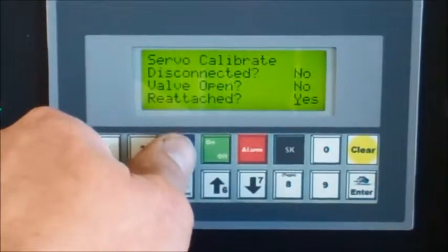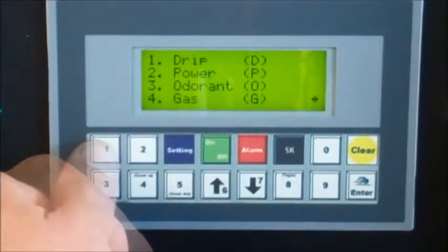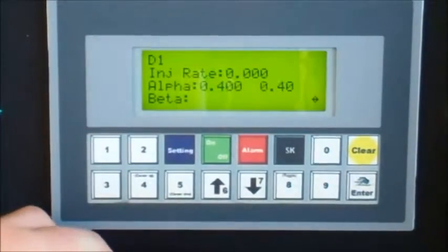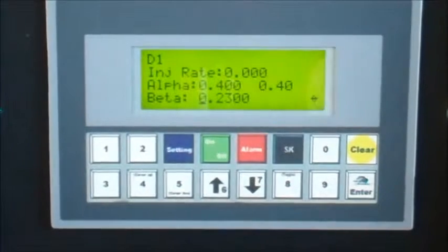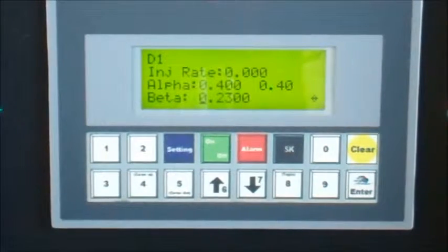You can at this point go back to the settings page. Press 1 to go back to the drip page. And now we will just wait for the servo to finish closing the valve. You can now open your valve on your odorant tank for the source of odorant to the unit. Okay, the servo is stopped turning.